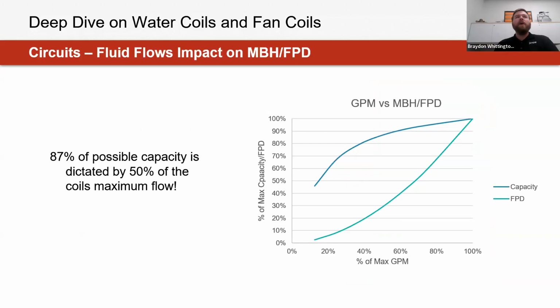A good way I'd say to visualize this at a fluid level, again, is a comparison of the maximum GPM that can go through one of these water coils versus the maximum capacity yield and how much additional fluid pressure drop that adds on our system. This is just evaluating a single circuit coil. And what we'll actually see when looking at these coils is that a maximum of 87% of our possible capacity of that coil is actually reached at 50% of that fluid flow.